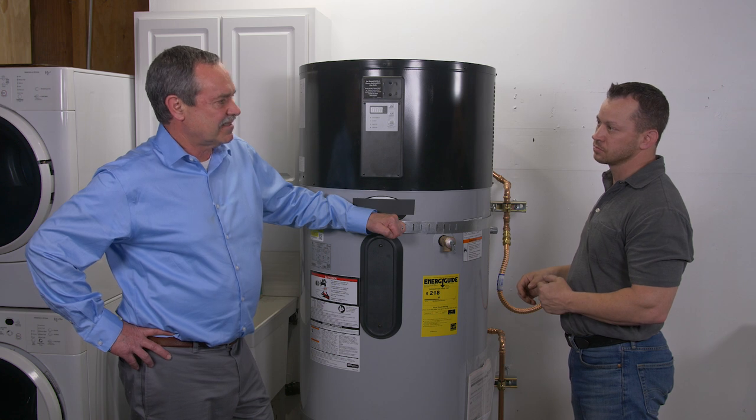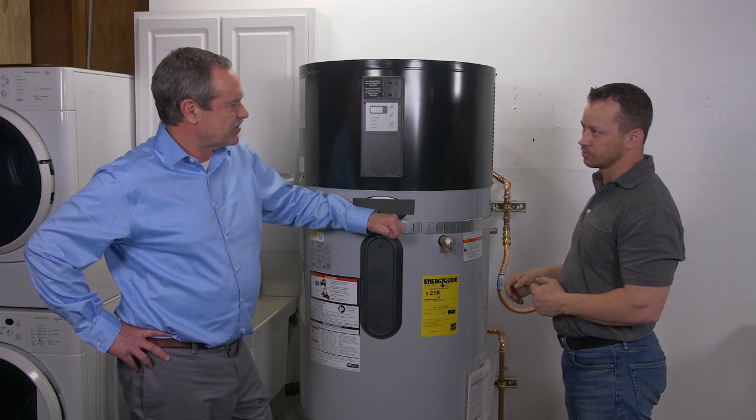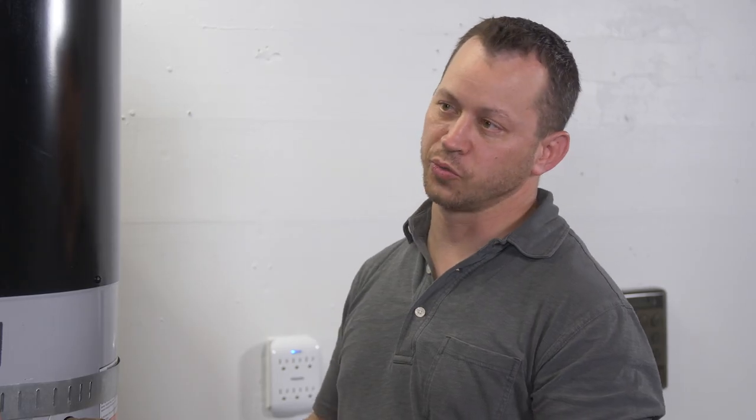Our next step is to run the condensate drain. I've heard the condensate might be acidic and you have to take special precautions before disposing of it. Well, that's only true when you're running a fossil fuel for your heat source. But since we're just drawing the heat out of the air, it's no different than the condensate on a cold glass of water on a hot summer day.